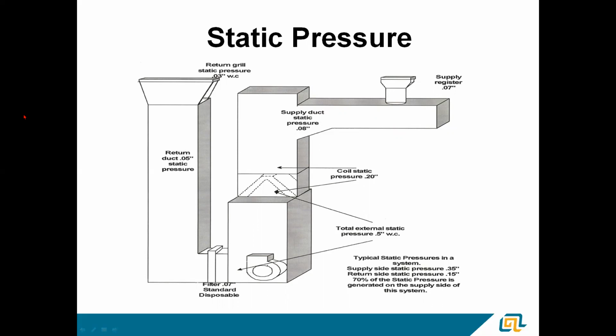We got some other numbers on there. For instance, the static pressure drop across the coil is about 0.2. I think that's for the older equipment, about 10, 12 years old. On the high efficiency stuff, I'm seeing coil statics closer to about 0.26, 0.28. That's our drop across the coil. The reason for that is they're trying to make these coils more efficient, and they've tightened up that fin spacing. It's a little harder to get airflow through them, and you're seeing a little bit more pressure drop across there.